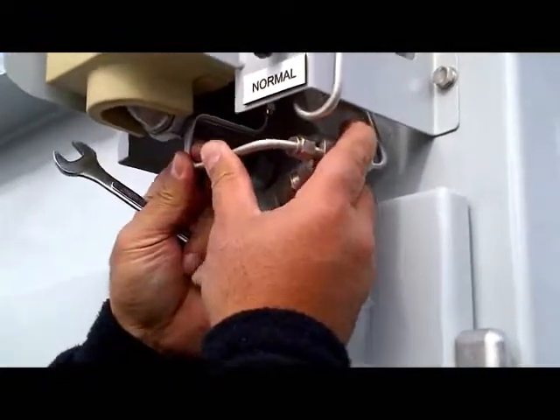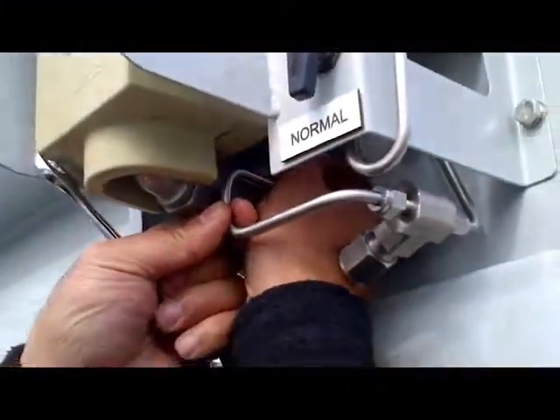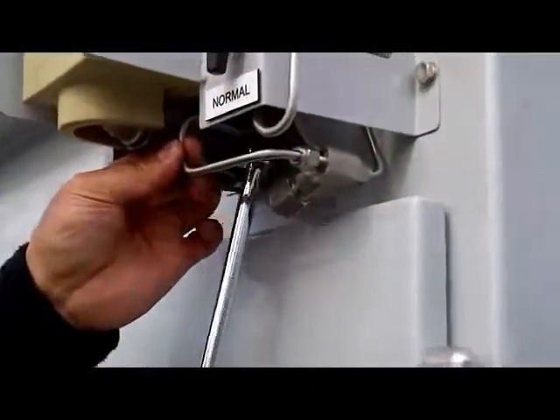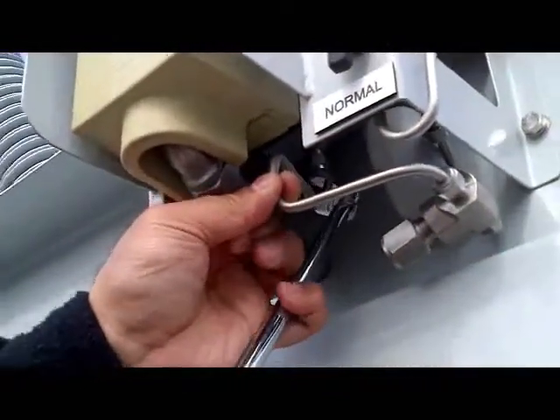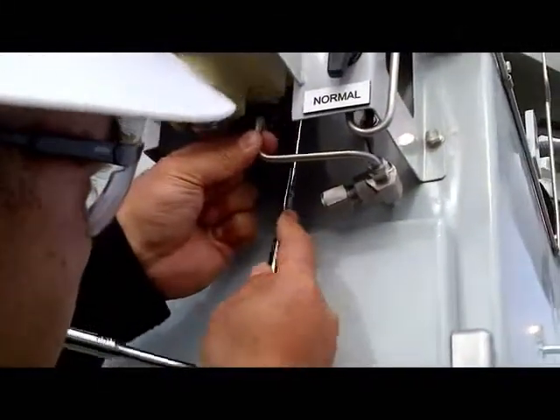Line it up perfectly and go all the way up tight. Make sure you hold it up tight before you turn the nut. Turn it all the way in hand tight. Hold it there. Then you bring your vertical swivel ratchet extension and just fit it through here. Turn this thing to adjust it again, so you have the right angle. Here you go. You hold it with one hand and start turning it in, and make sure you push the tube upright so it doesn't slip back.